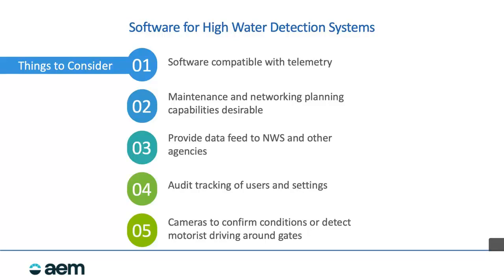Audit tracking of users and settings is really critical for these mission-critical systems. We want to document if someone turned off an alarm, raised the alarming threshold, or deleted a data point. This kind of tracking is critical, especially following an event—for example, if someone asks why a text message wasn't received in the middle of the night, we can see that a person deleted it, investigate why, and adjust privilege levels so that doesn't happen again.